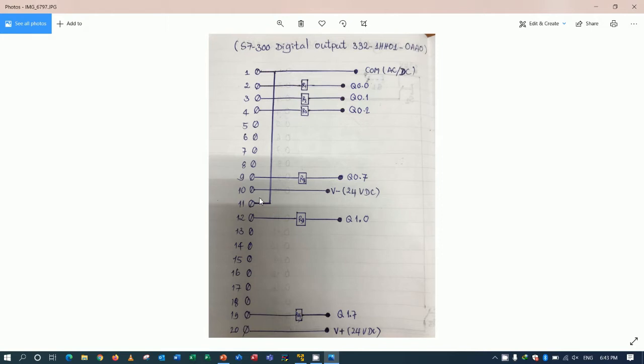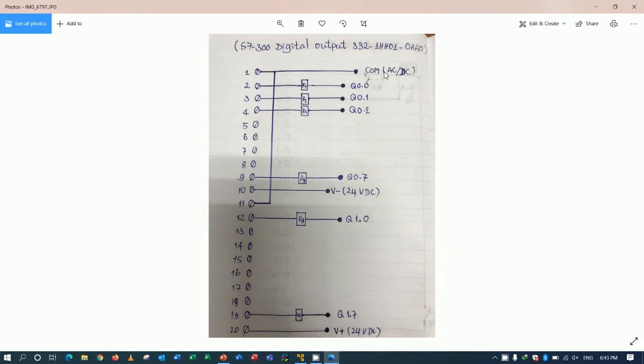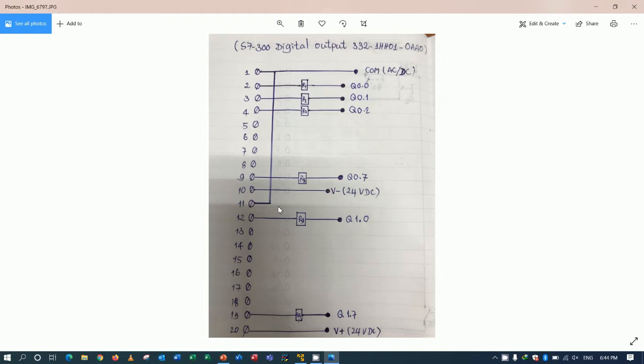So terminal number 10 and terminal number 20 is 24 voltage. And for terminal number 1 and number 11, we can use AC or DC to match with our plan. For example, we can control the relay or contactor with AC, we can connect AC. And if we would like to control the relay or some electrical devices with DC, we can use DC to connect the terminal number 1 or terminal number 11.